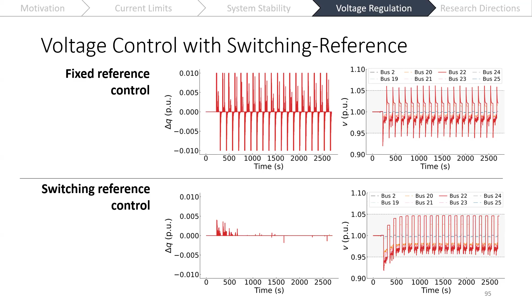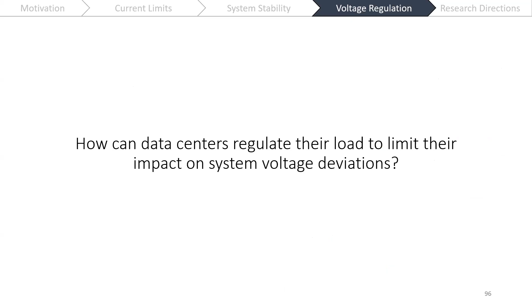However, you might still notice we have large steps in our voltage, so this motivates having some more control, at least on the active power side, and some internal regulation of the data center. So the question we ask then is, how can data centers regulate their own load to limit their impact on system voltage deviations? Even if we're running some kind of reactive power compensation like this, we want to minimize those voltage deviations, so we're going to want to minimize the steps in our load.